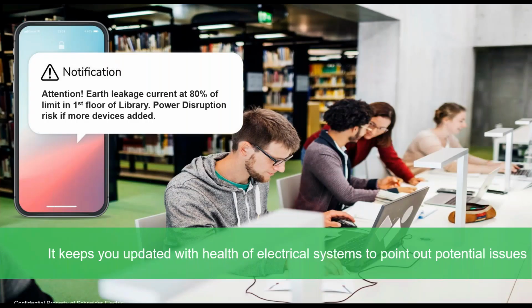So we introduced you to Acti9 Active, or the active safety system. Let's see in a little example what this system can do. It can offer you a notification: "Attention, earth leakage current is at 80% of the limit in the first floor of the library. Power disruption risk if more devices or circuits are added." It keeps you updated with the health of the electrical systems to point out potential issues.